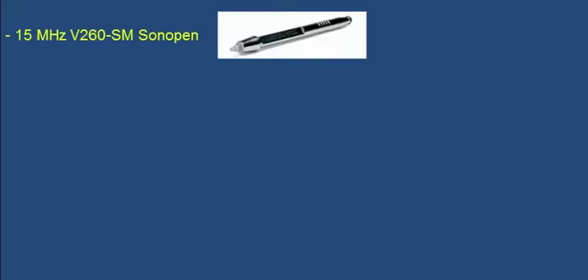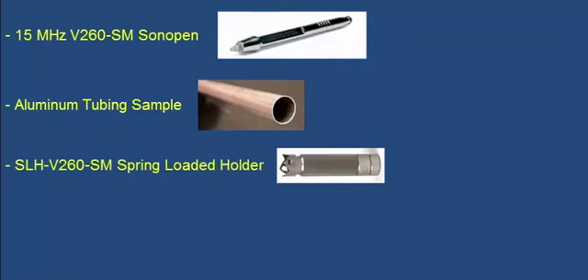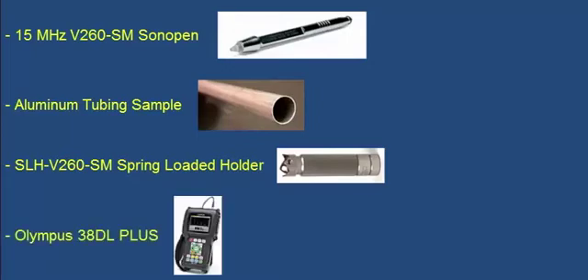In this demo, we will first show how to set up the 15 MHz V260-SM Sonopen Delay Line Transducer to make measurements on a 0.362-inch or 9.2-millimeter diameter aluminum tubing sample with a wall thickness of 0.013 inches or about a third of a millimeter. Since we are going to be measuring small-diameter tubing, we will also use the SLH-V260-SM spring-loaded V-notch holder. For this demo, we will use an Olympus 38DL Plus thickness gauge. The exact key presses would be different if you were using a different model Olympus thickness gauge, but the overall process would be the same.